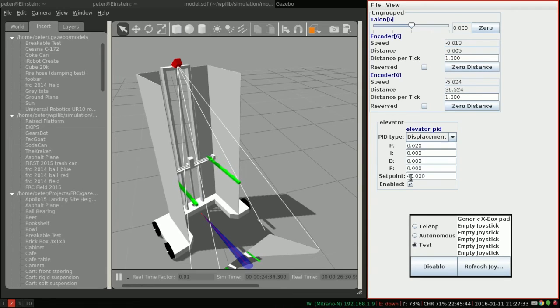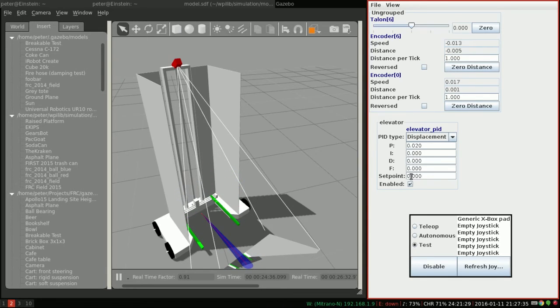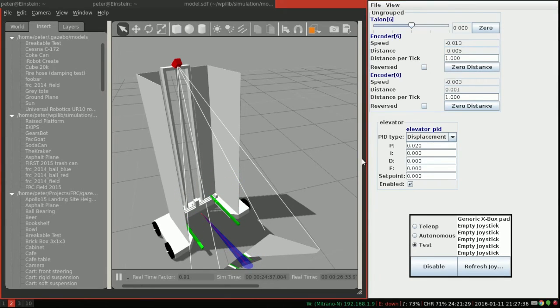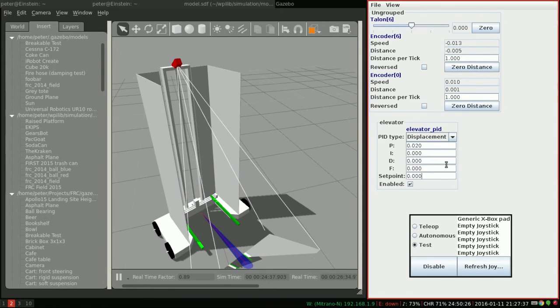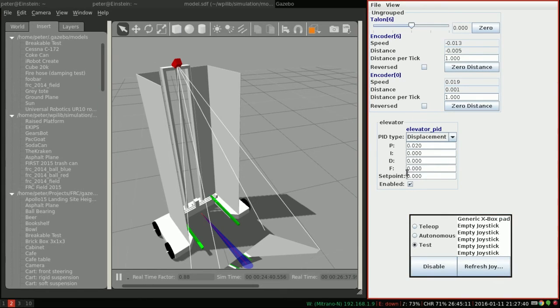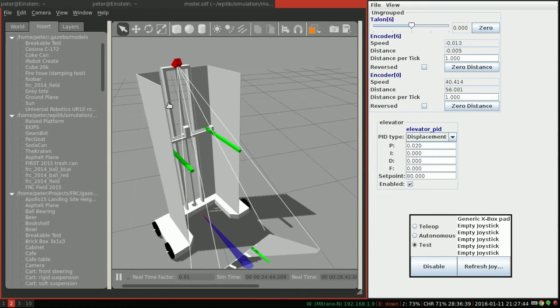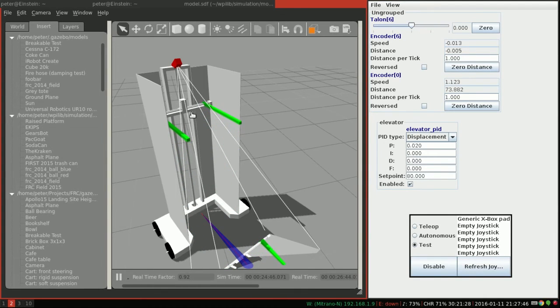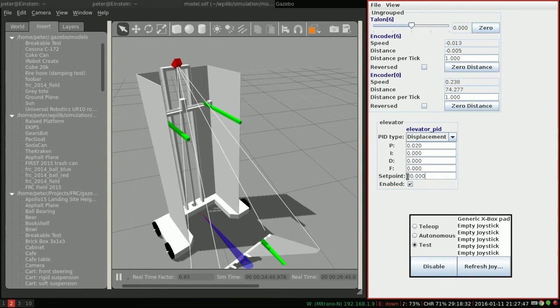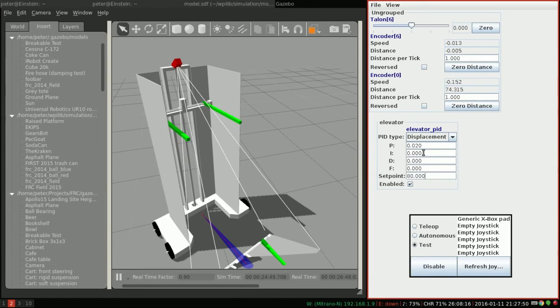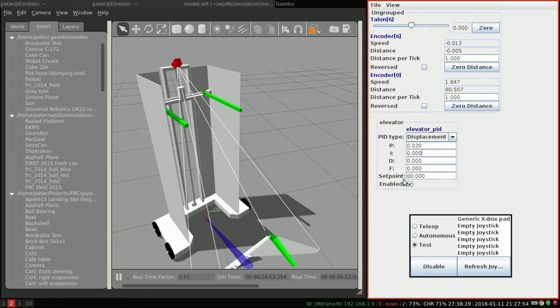Now, one thing to remember about the integral term is that it's time-based. So if I have a longer set point, such as 80, which is right near the top, we're going to have more accumulation of error. Which means this I term is going to have a bigger impact. Keep that in mind when you're tuning your PID.